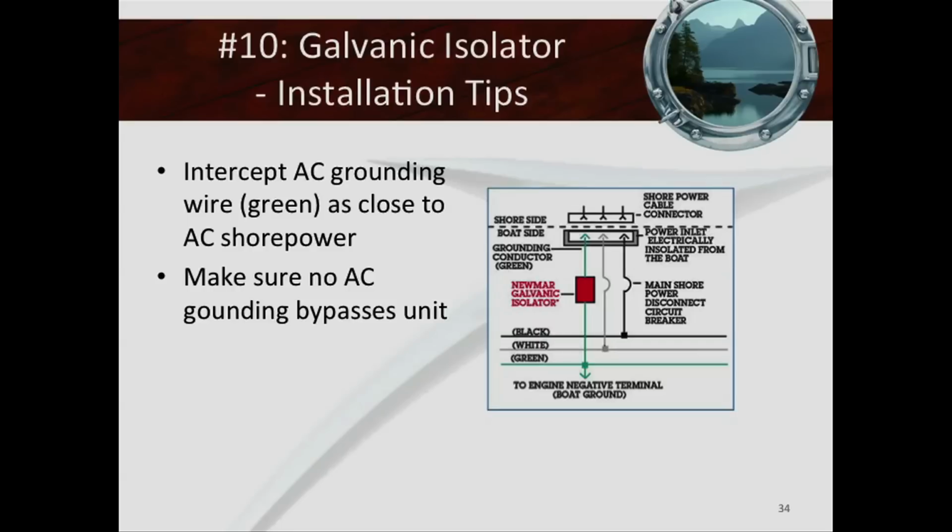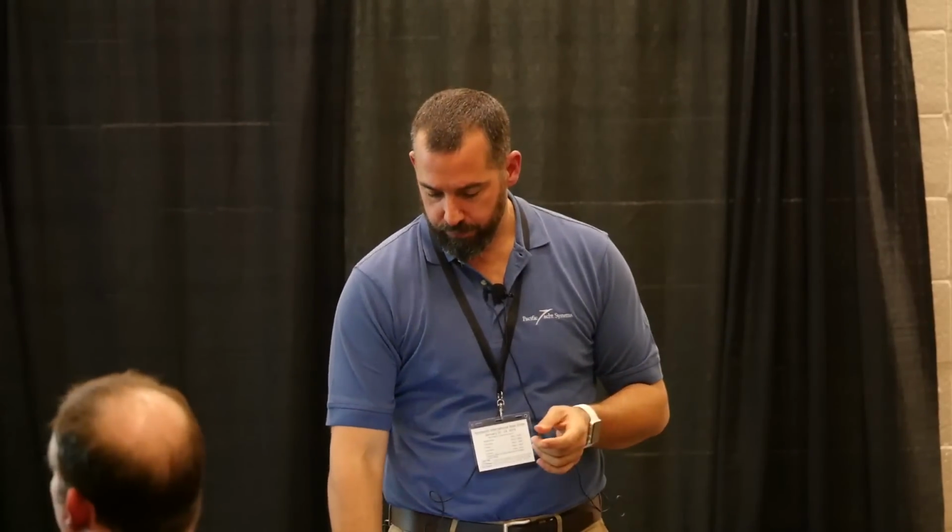I've got clients that say to me, oh, well, I'll put it somewhere from A to B, and I know where B is, but I'm like, do you know from A to B, are you certain that that wire was never intercepted? Right? And the question is, maybe you take a chance, and there's nothing wrong with it, but if it was intercepted, the diode, the fail-safe galvanic isolator is not going to be effective because something is going to be able to bypass it. So it needs to be a choke point. The only way to make it a choke point is to have it as close as humanly possible to the receptacle, and you know for a fact that nothing can bypass it. And that's how you make sure that it works.